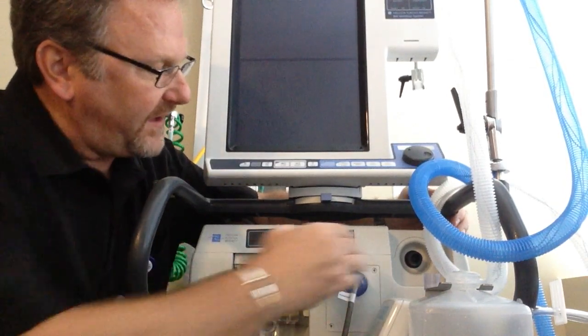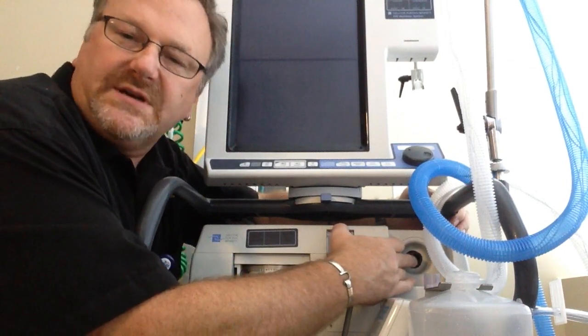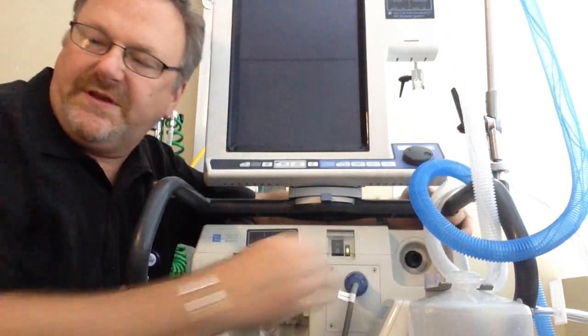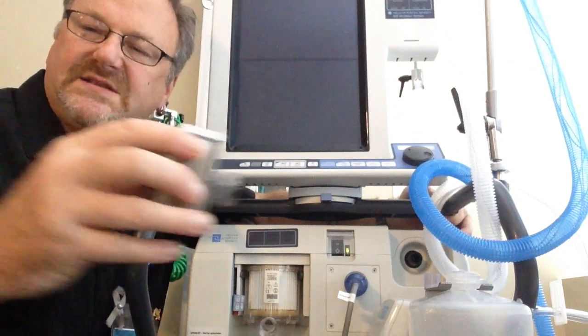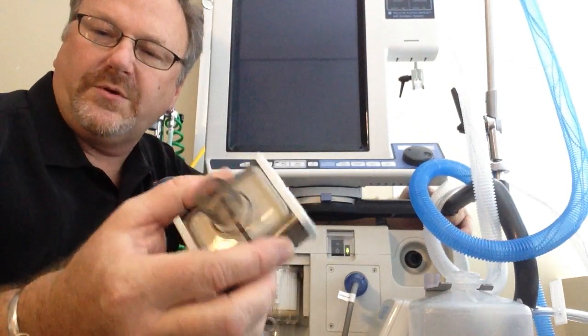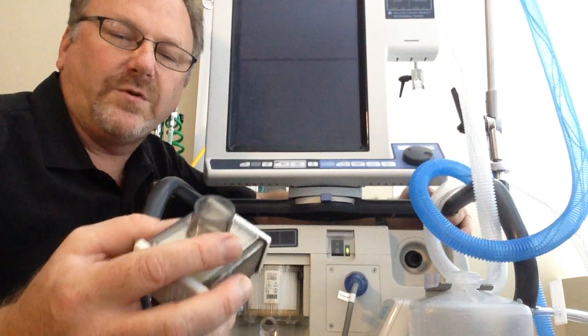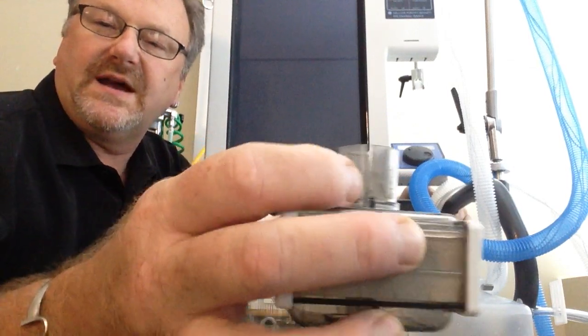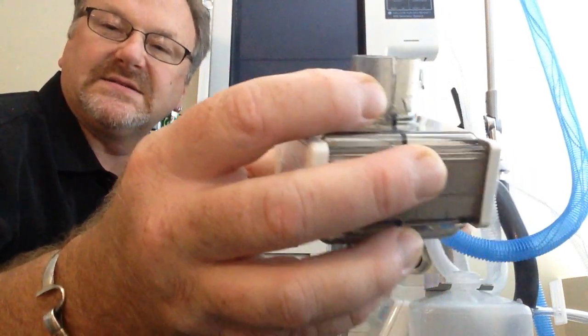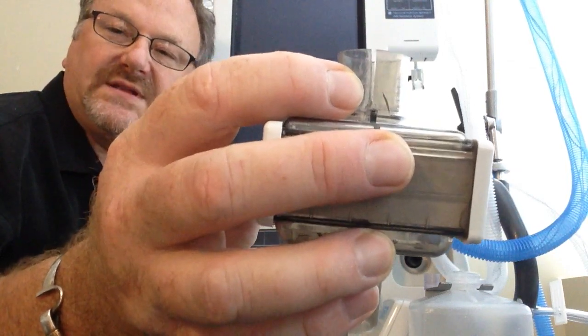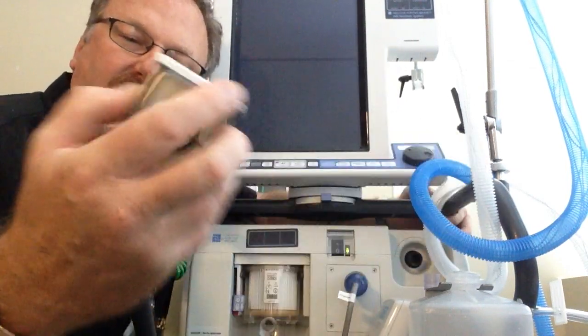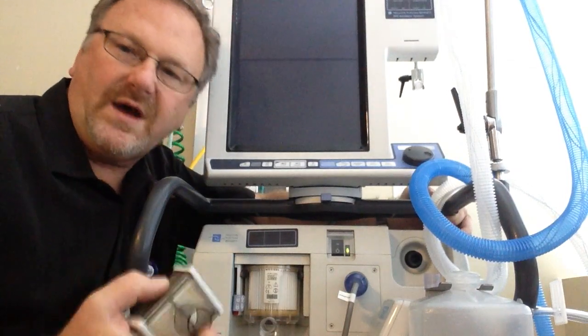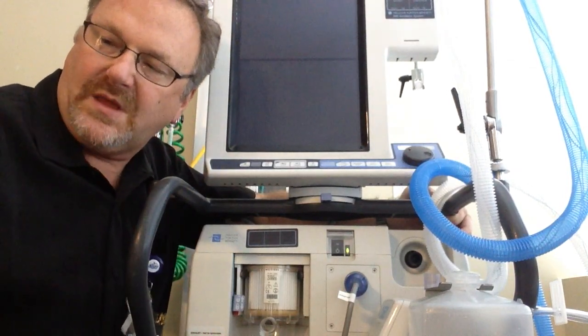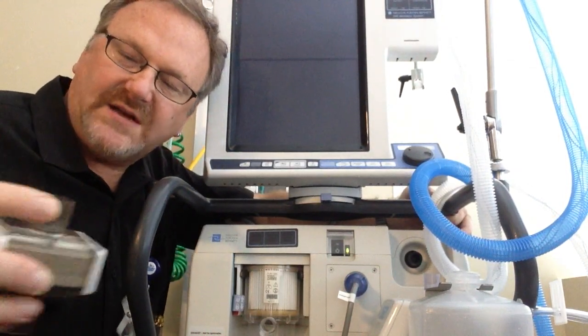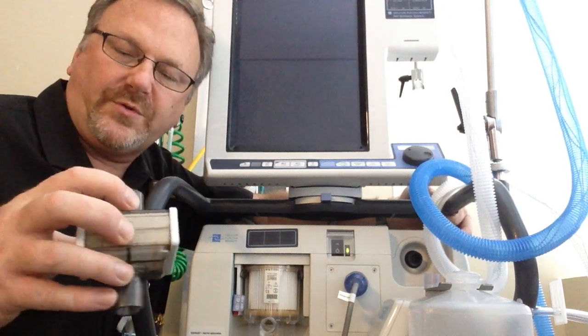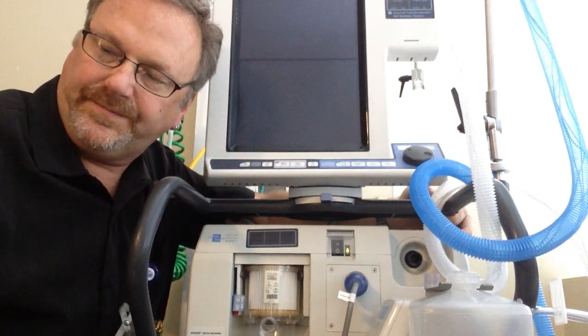You then have to put a filter on the inspiratory side, which is from the ventilator to the patient. This is the filter that is made for the Puritan Bennett 840. Unfortunately, one of our students got a little zealous, and you can see that crack. Due to that crack, this filter leaks and it will not pass the pre-use tests. So if this were to happen in a hospital and you cracked it, you would have to redo the pre-use test and get a new filter.